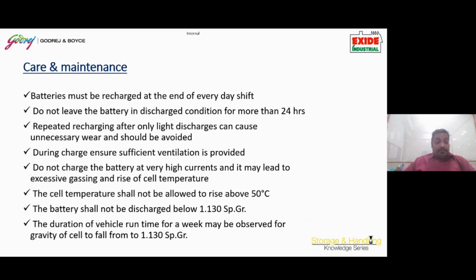For the duration of vehicle runtime, the gravity of the cell may be observed to fall from 1.32 specific gravity to 1.130 specific gravity. In case the gravity drops to 1.130 every time, then this pattern needs to be analyzed, and probably the cell is giving a sign of failure. The OEM should be informed, and a team from the OEM should come, inspect the batteries, analyze the root cause and take the necessary action to correct this.